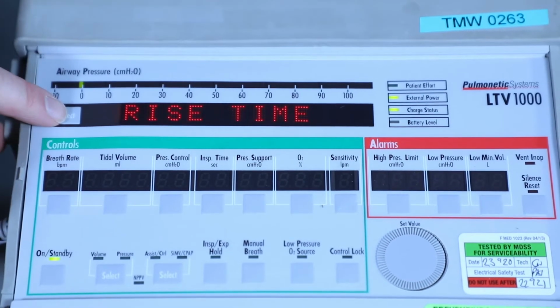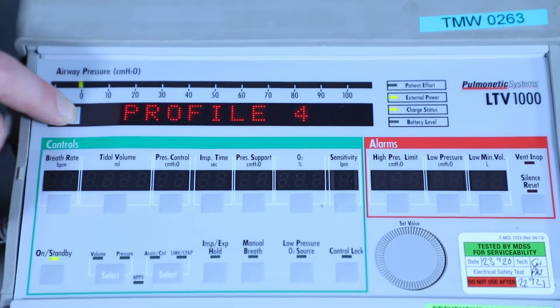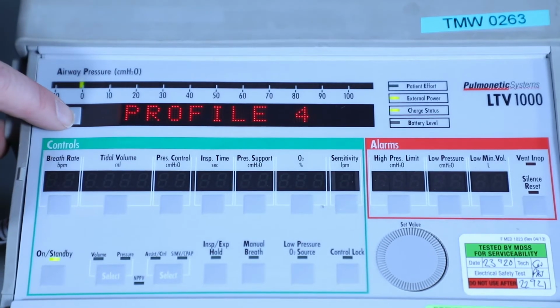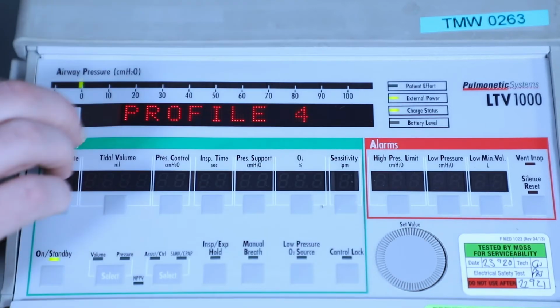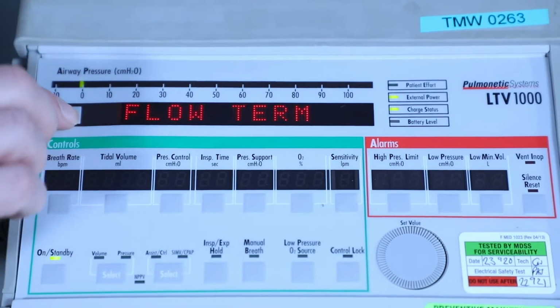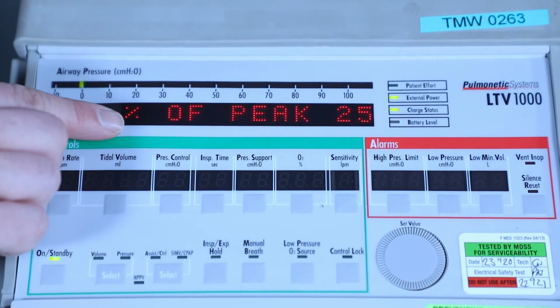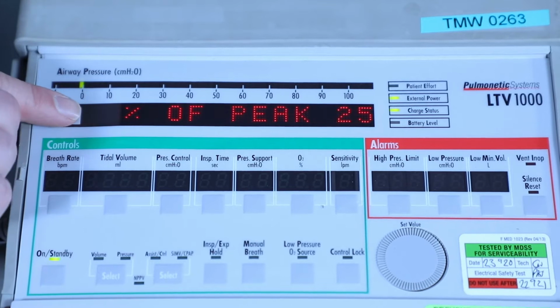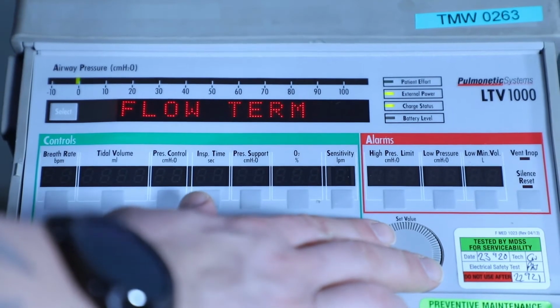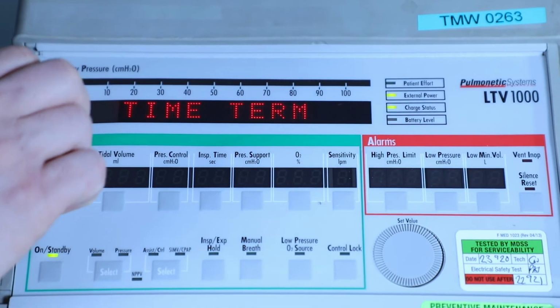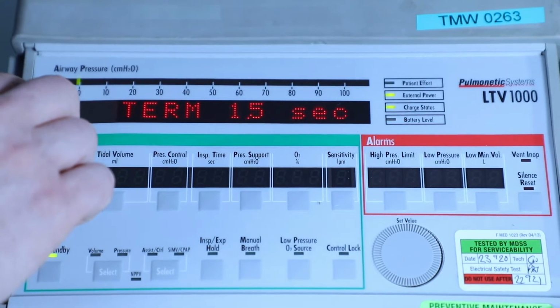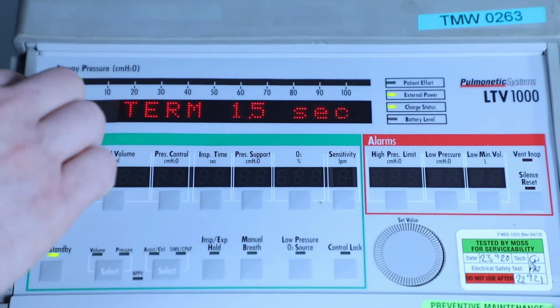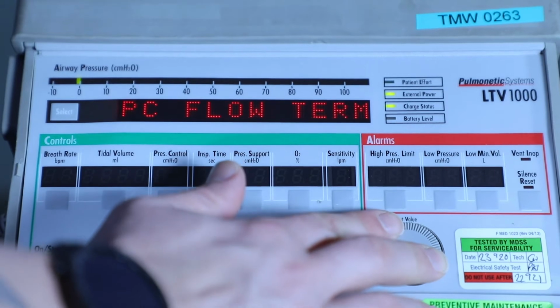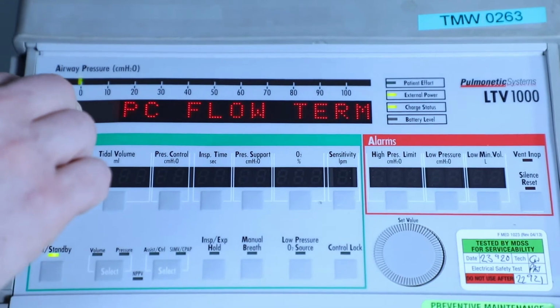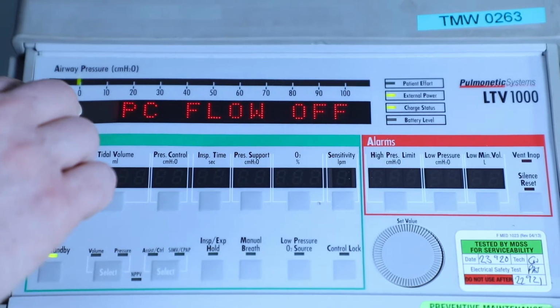Again, scrolling through each of the menus to ensure that the correct parameters are set. Rise time is set to profile 4. This has a range of 1 to 9. Flow term set to 25% to peak flow. It has a range between 10 and 40%. Time term, this is a range between 0.3 and 3 seconds. We have it set at 1.5 seconds. PC flow term, we have selected for off, and it switches between on and off.